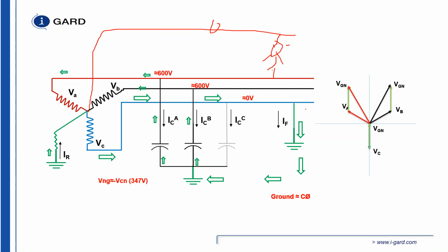So the voltages shift with respect to ground such that the unfaulted phases, A and B, are 600 volts above ground, and C phase is 0 volts, but more importantly, the neutral is going to be at 347 volts above ground, and we have not isolated it at this source or for this load.